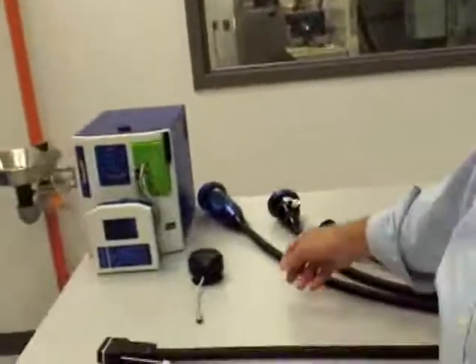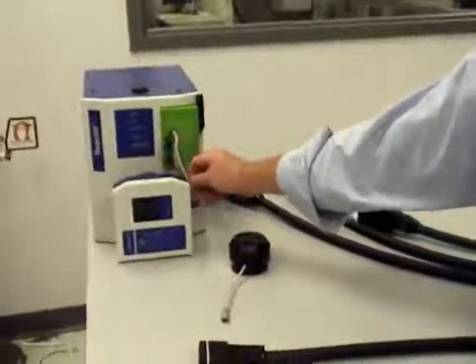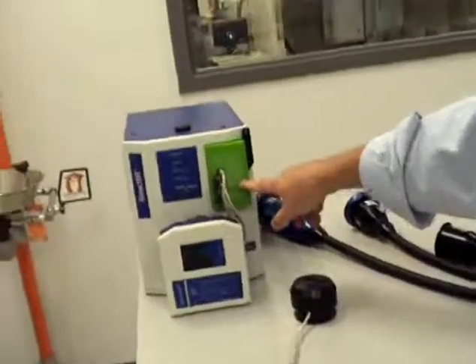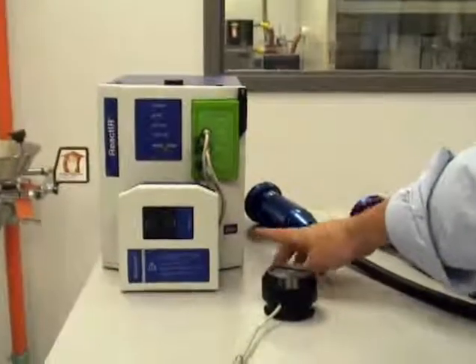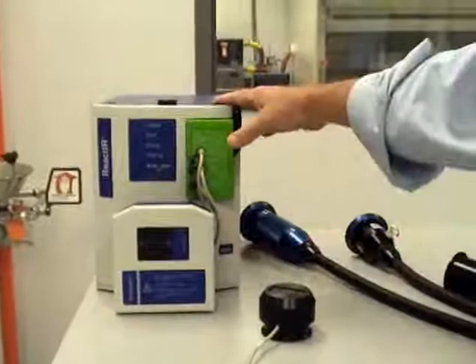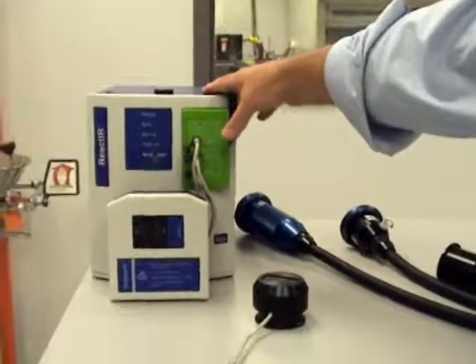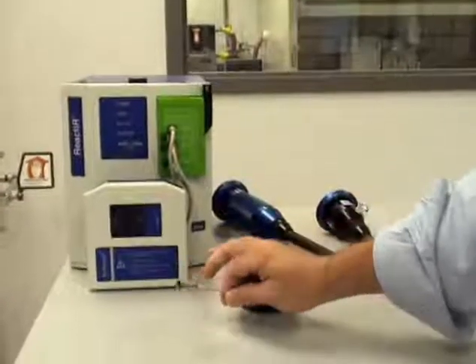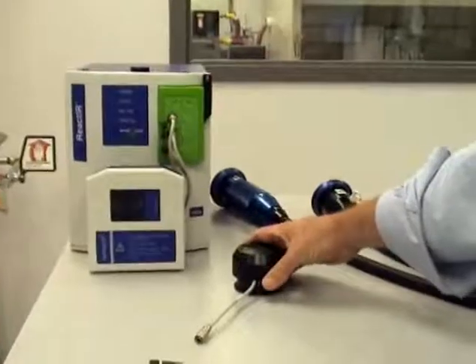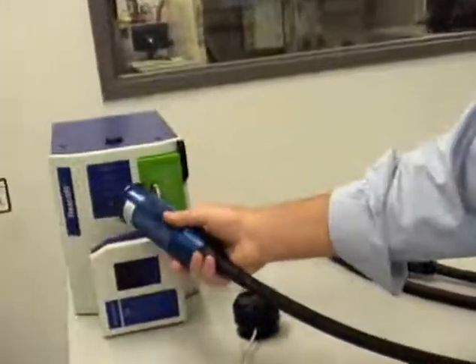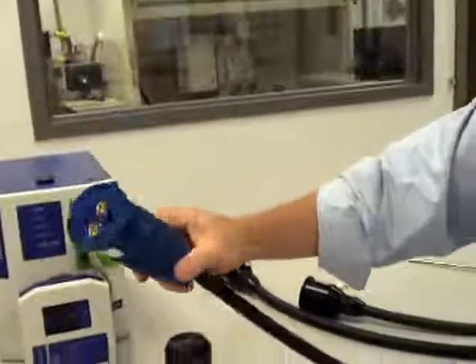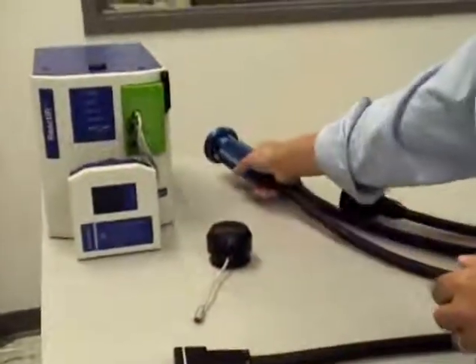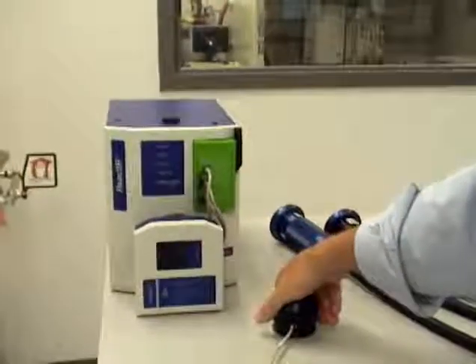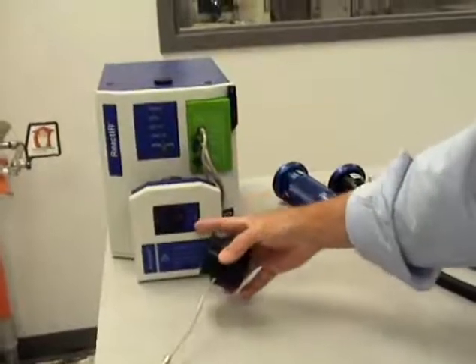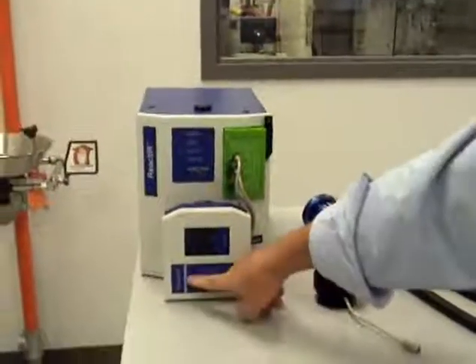Over here we have the cord, because you can see there's an RTD1 input and an RTD2 input. This is the ReactIR 45M, which we introduced 2 years ago. Because it's newer, it has the capability and electronics necessary to capture temperature information, so we need the cable. This instrument can accept either this older style sampling technology, similar to the mirrored conduit, where we simply connect this to the silver flange and clamp it down.